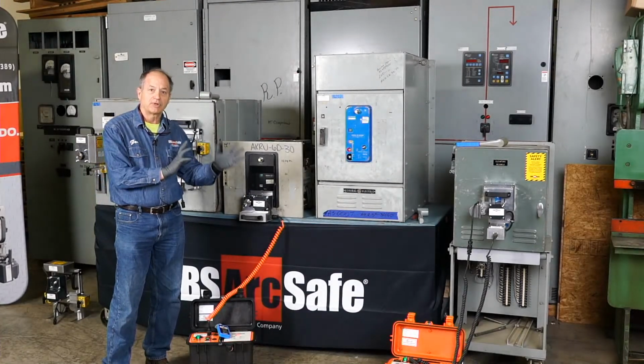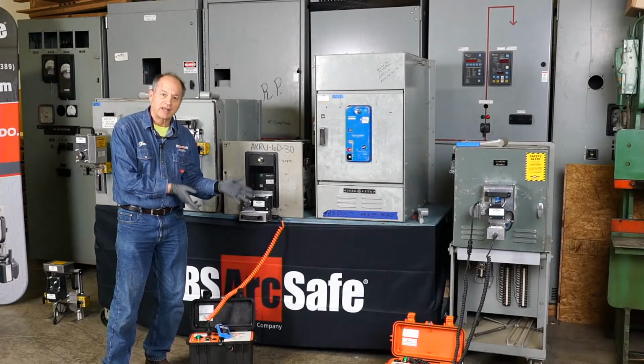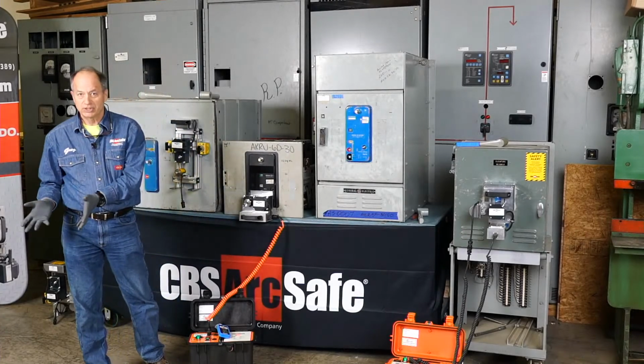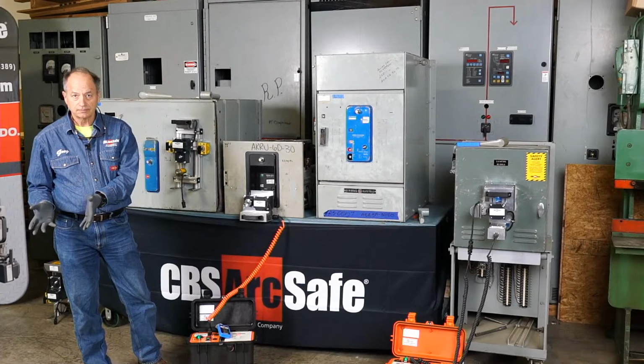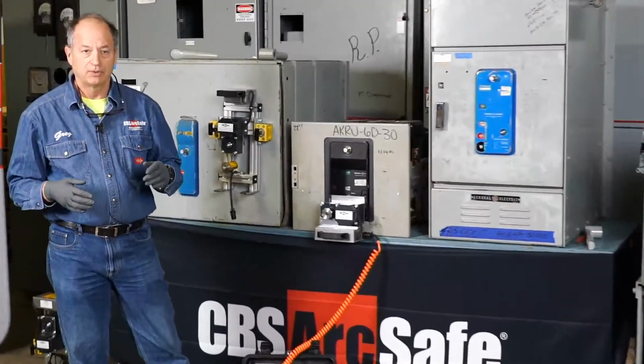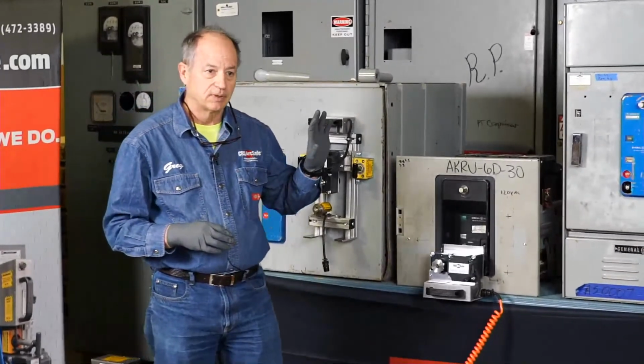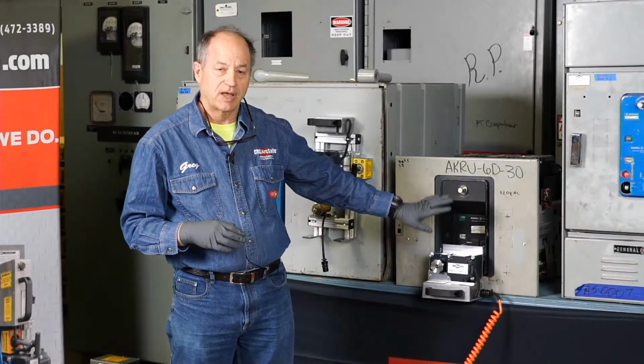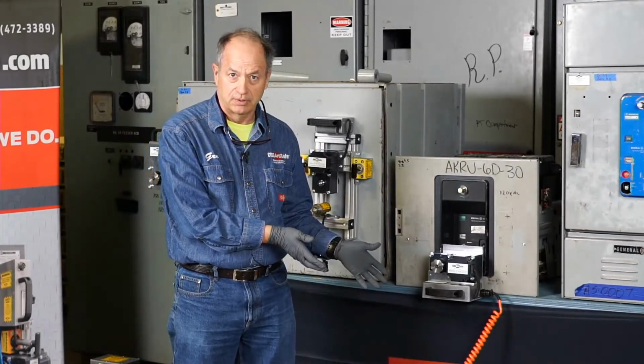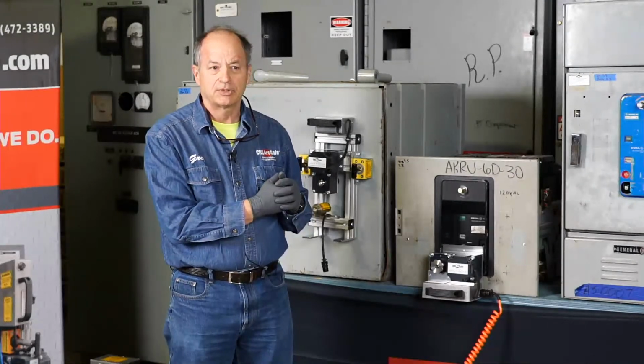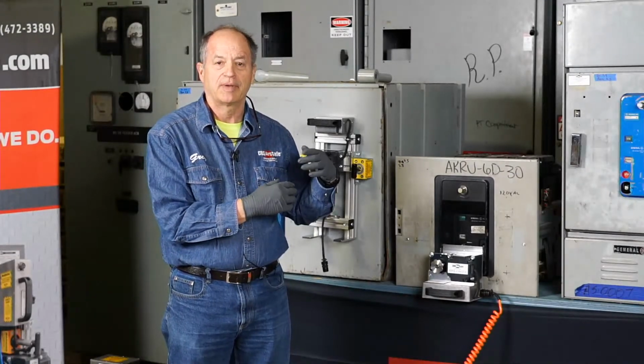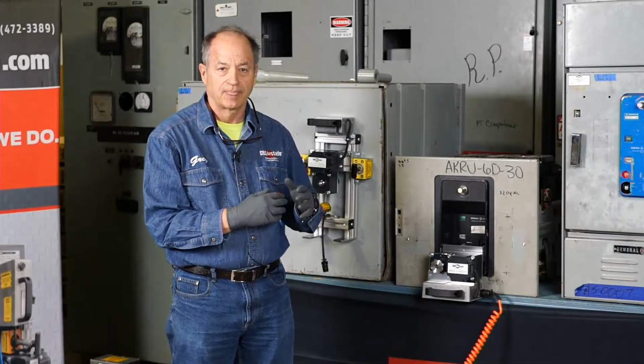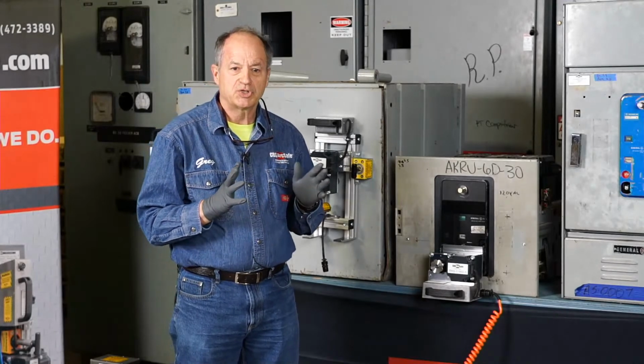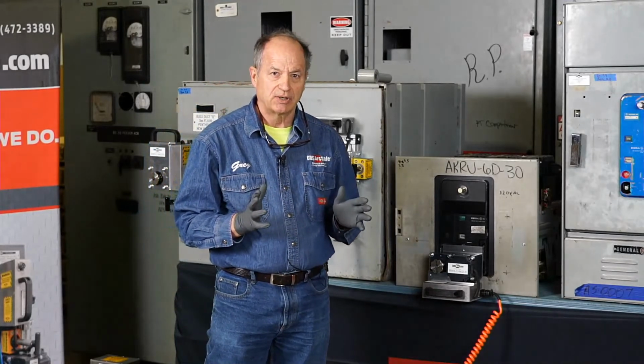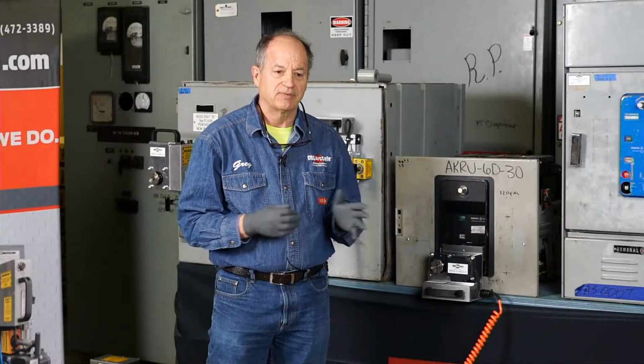So it's broken down to task specific: a remote racking device and a remote switching device. You don't want to let somebody try to rack a breaker without making sure it's open first. You don't want to let somebody charge, close, and trip the breaker without making sure it's in the proper position. So you're not out to try and speed up operations necessarily, you're out to keep your people safe.